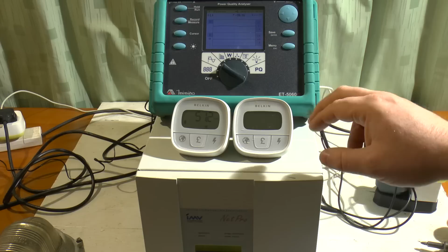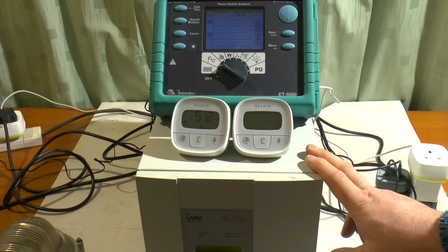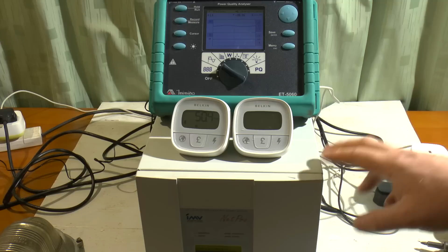If you're going to use this for load shifting, charging it up on economy 7 and running it during the day, be aware that according to the instructions this particular model only kicks out 1.5 amps on the battery charger. So you're talking about 110 watts of charging. So in a 7-hour period you're going to get not even a whole unit of electricity charged into it. So you're going to need an external charger as well as an external battery pack. And also worth considering, when it's switched off it's drawing around about 50 watts.